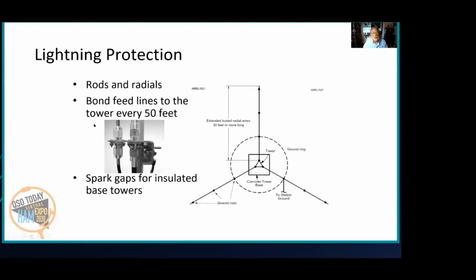On the tower, you want to bond your feed lines to the tower every 50 feet or so. It's kind of a pain in the neck, but if you get a hit on a tower and the current is flowing down that tower and it's got some inductance, you can have 100,000 volts between the top and bottom of a 50-foot tower from a lightning strike.